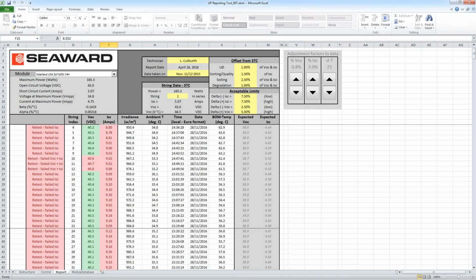Andre asked me, can I use the Solar Utility Pro as an IV curve tracer or just as a VOC ISC tester with the irradiance and temperature compensation? No, the IV curve tracing is really a different test process. What we do is we short out the circuit and then we vary a resistive load on the string and take points of current against voltage to give us the characteristic IV curve, the IMPP, the VMPP, and the max power point. If we're just taking the 2 endpoints, so short circuit and open circuit, we can't get a curve trace.